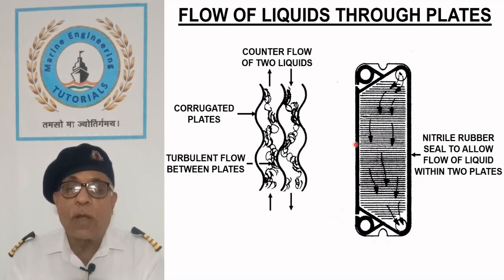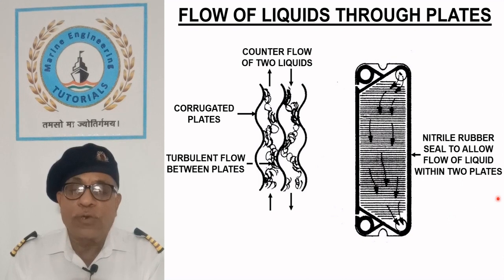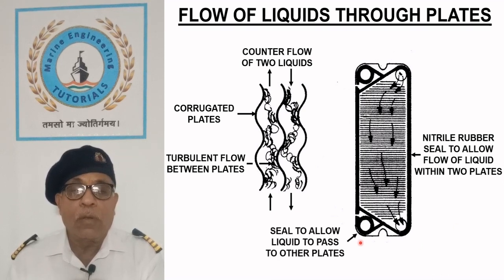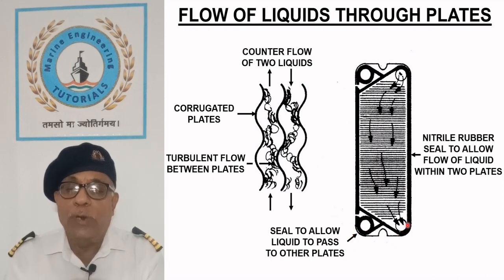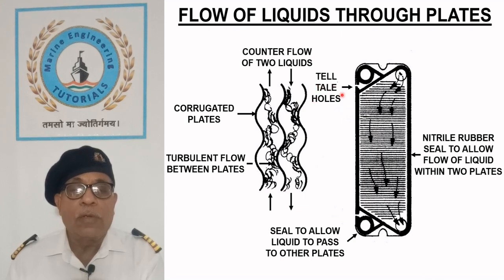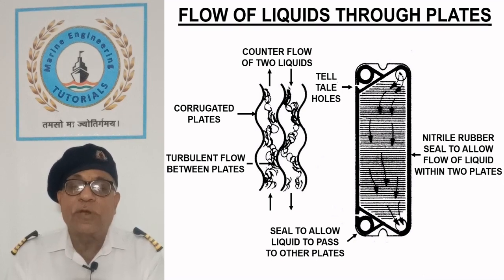The nitrile rubber seals are bonded to the plates by suitable adhesives. Removal is facilitated by application of liquid nitrogen, which makes the seal material brittle so it can be broken. Seals allow the two liquids to pass through in alternate plates without intermixing. Nitrile rubber is suitable for temperatures up to about 110 degrees centigrade. At higher temperatures, the rubber hardens and loses its elasticity. Telltale holes provided in the seals prevent intermixing of the two liquids and reveal damage to the seal by external leakage of the liquid.